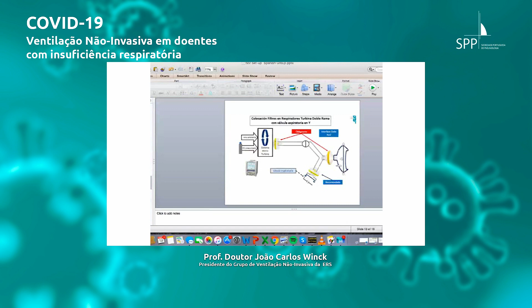But if you have to use helmet, you can use the configuration that Bill Troschel told you this morning, or you use a conventional Venturi system. It's easier. If you want to use helmet, if you have the possibility to get some helmet, the easiest configuration is a Venturi. There is a Venturi system from one side of the helmet, then you put a filter and the PEEP valve. End of the story.